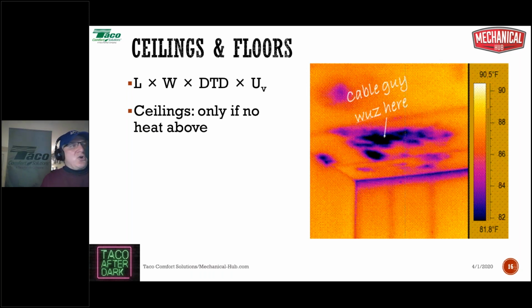If you have a cold attic, then yes, you're going to have to do a ceiling loss. Look up in the handout and you'll find a U-value for an attic assembly. If you have a built-up roof/ceiling, where one side of the ceiling is inside and the other side is the roof, with outside on the other side of that roof, you've got a cold lid and have to do a heat loss calculation for the ceiling.